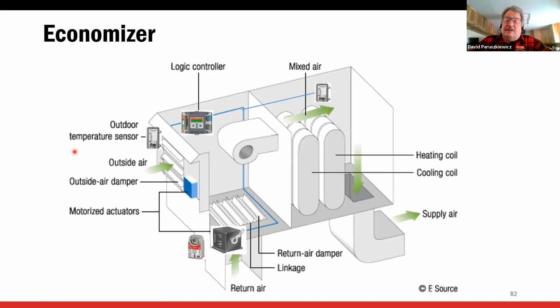Okay, economizers. We're going to take a quick look at economizers and this new Jade controller here. If you haven't worked with it yet, they're really simple once you dive into them. We're going to spend a couple of minutes on this Jade control. The economizer is pretty straightforward. Here's my rooftop unit. Instead of my return air going across my evaporators with my compressor running, if the outdoor conditions allow, meaning the temperature and humidity outside are lower than inside, the compressor will lock out. These return air dampers will close, and at the same time these outdoor dampers will open. The fresh outdoor air will go down into the building. That's what an economizer does.